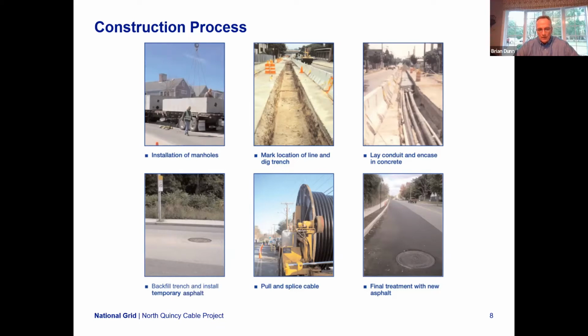The crews will start with that, and then come behind to put in the conduit and duct bank. They'll saw cut the pavement, dig the trenches, put the conduit in as the top picture shows. That'll get backfilled, and then we'll resurface or put the final trench patch on. I know it says temporary asphalt, but we're installing it more as a permanent condition, because there could be several winter seasons between when the conduit and duct bank system is installed and when we get to final paving.